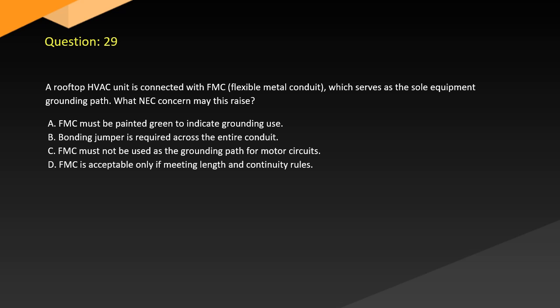Question 29. A rooftop HVAC unit is connected with FMC, flexible metal conduit, which serves as the sole equipment grounding path. What NEC concern may this raise? A. FMC must be painted green to indicate grounding use. B. A bonding jumper is required across the entire conduit. C. FMC must not be used as the grounding path for motor circuits. D. FMC is acceptable only if meeting length and continuity rules.